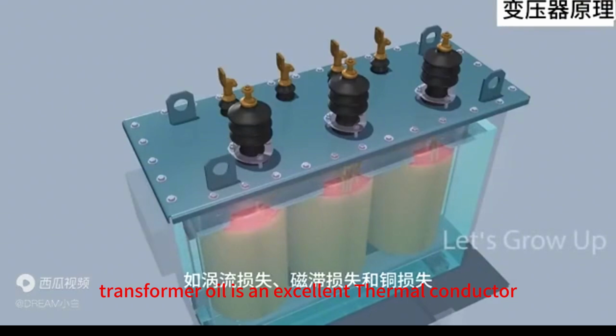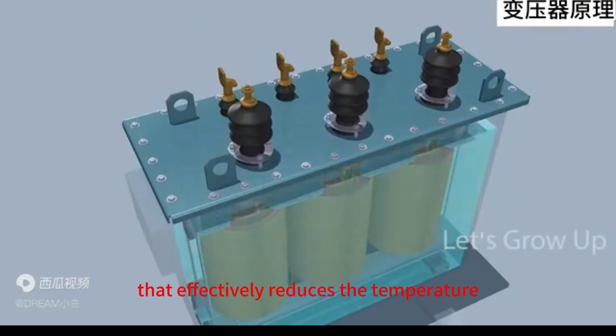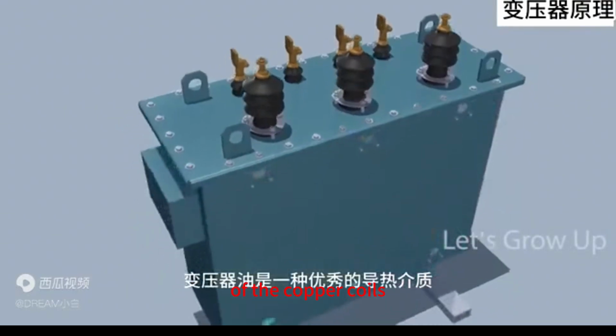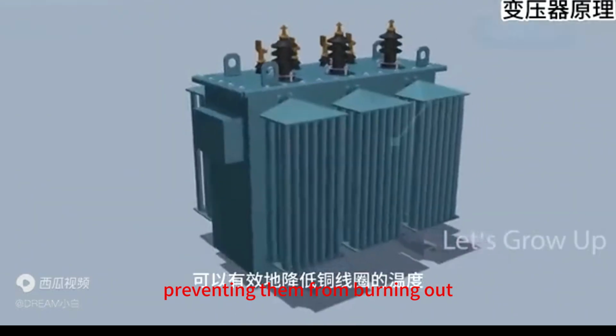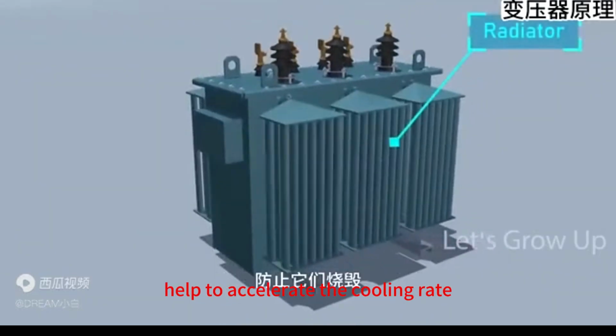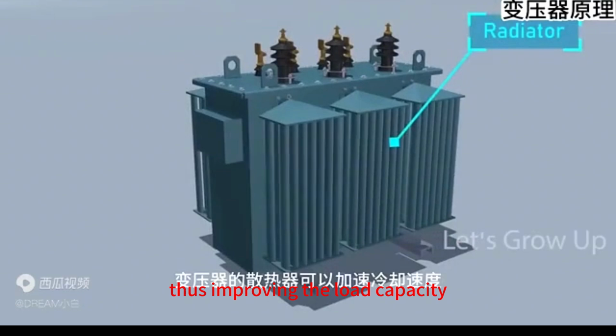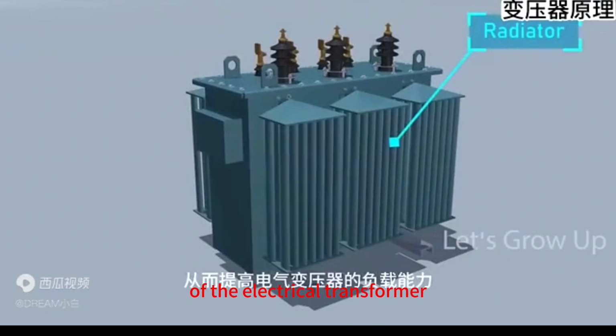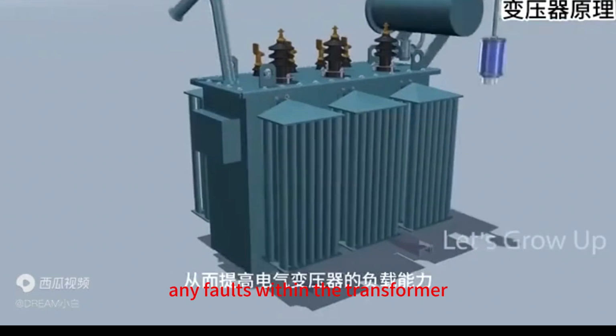Transformer oil is an excellent thermal conductor that effectively reduces the temperature of the copper coils, preventing them from burning out. Radiators on the transformer help to accelerate the cooling rate, thus improving the load capacity of the electrical transformer. Buchholz relays are used to detect any faults within the transformer.